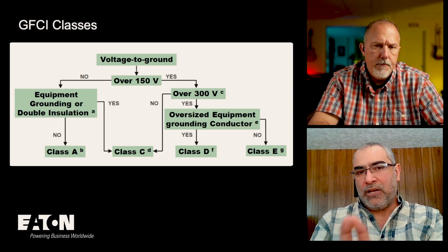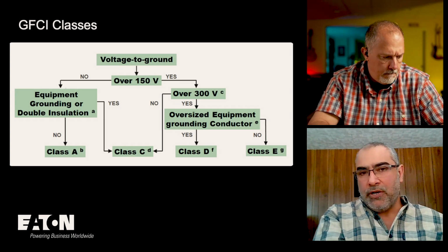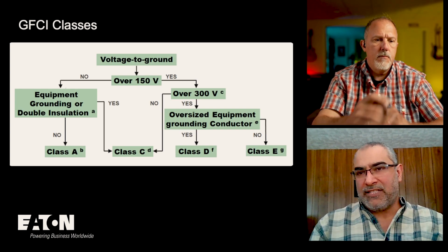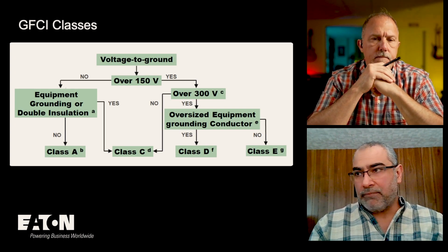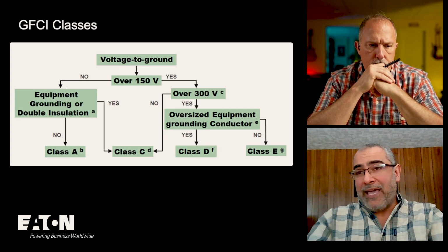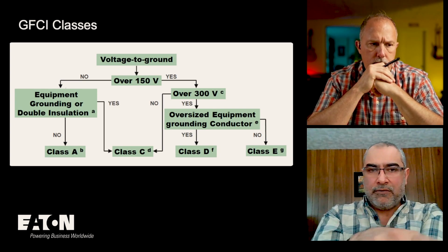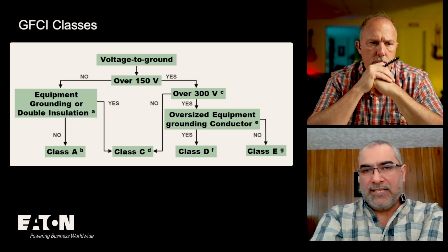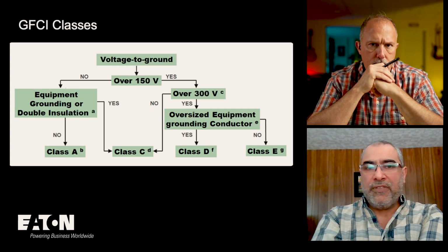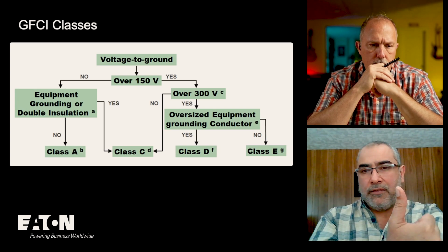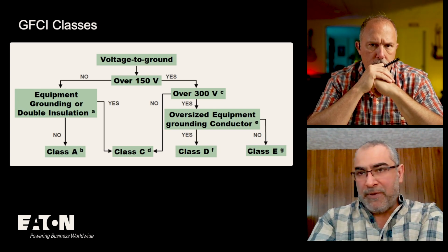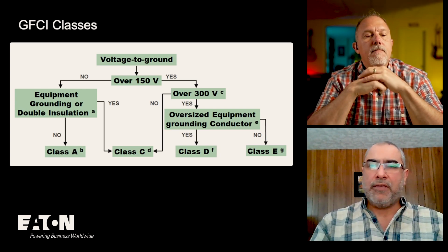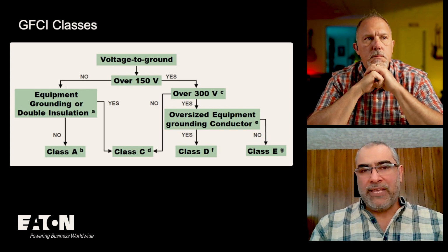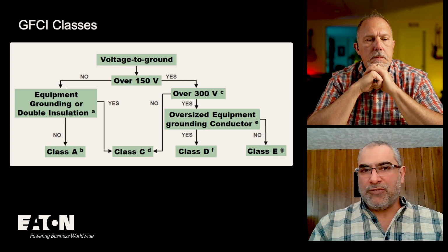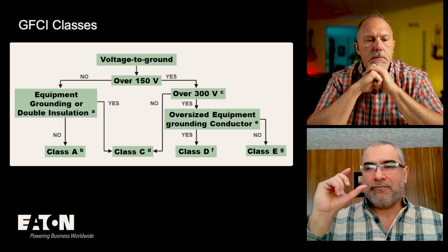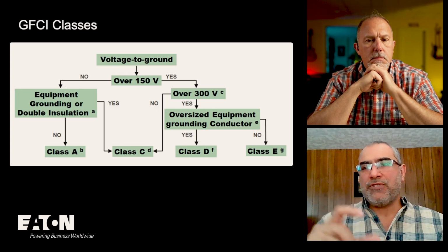Like you can't install a Class C, let's say, C you can, but Class D you can't install on a 120 volt circuit, like you have at home, for example. But Class C you can, because there's an exception that you can use it; the flow chart is showing less than 150 volts. So if the voltage is right and there's no nuisance tripping because of the 6 versus the 20 milliamp, you can use a Class C, and pretty much in all the applications you can use Class A. So special purpose should not imply that they're only used in special applications.